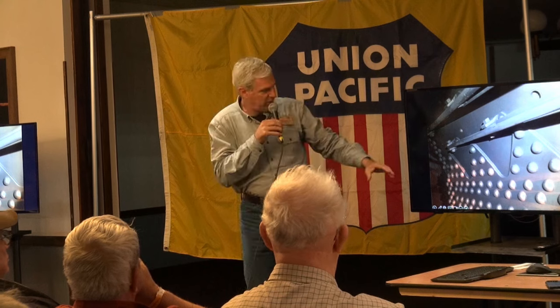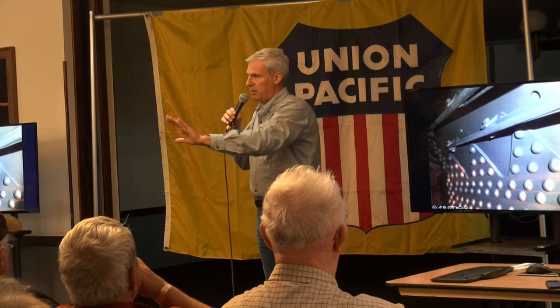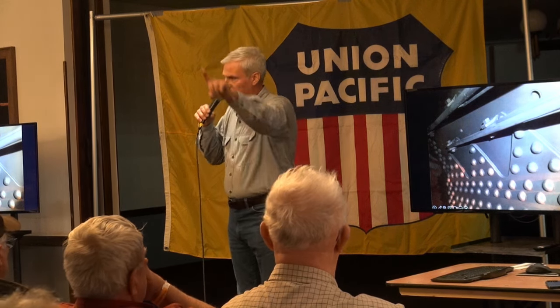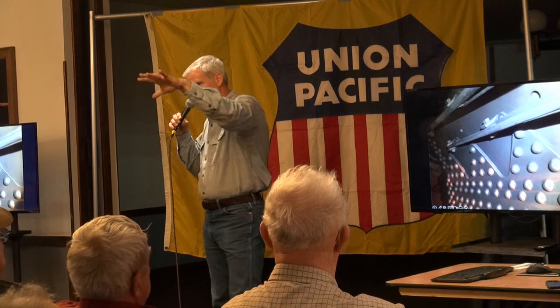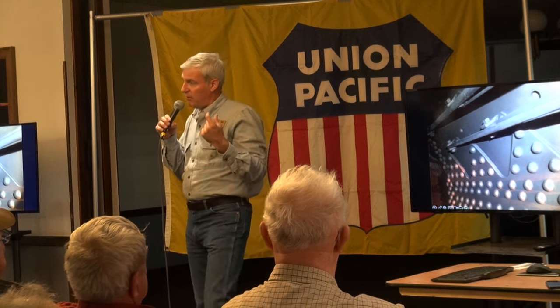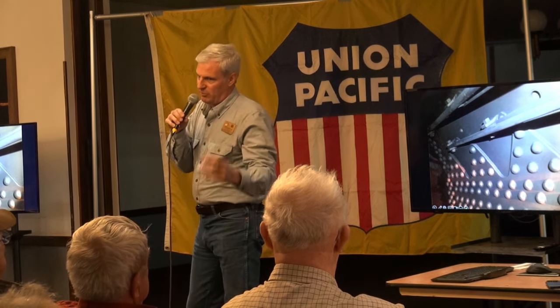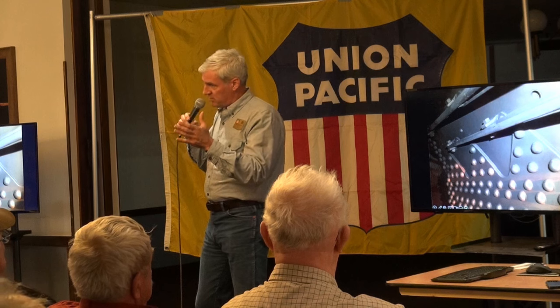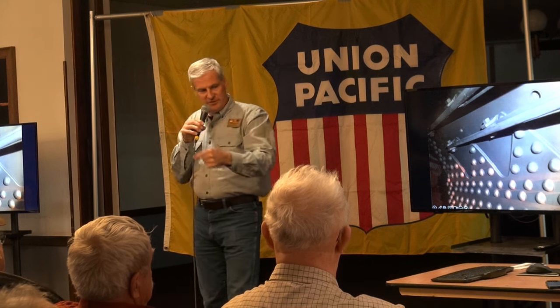Well, the steel itself, when it's rolled into a cylindrical plate, that structure is self-supporting. And you've got these big reinforcing plates called liners, and they're riveted here, and that's how the boiler's held together. When you get to the firebox end, that is no longer a cylindrical structure, it's rectangular. And there's some radiuses in that structure. Well, now you've got 300 pounds per square inch of pressure. And if you do the calculation on the stay bolt loading, you're like 7,400 pounds. This is a tremendous pressure that steam is exerting at all times. So that metal plate is held together with all those stay bolts.